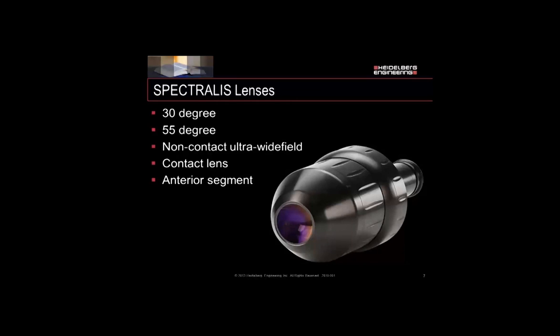The lenses available for this system are the 30-degree lens, which is standard with all systems, the 55-degree, our new Ultra Wide Field lens, and also our contact Ultra Wide Field lens — the Staurenghi lens — and the anterior segment lens. We're not doing Wide Field imaging with an anterior segment lens, so we won't discuss that. And since Sturangi is a contact lens, we're going to focus on these three non-contact lenses.